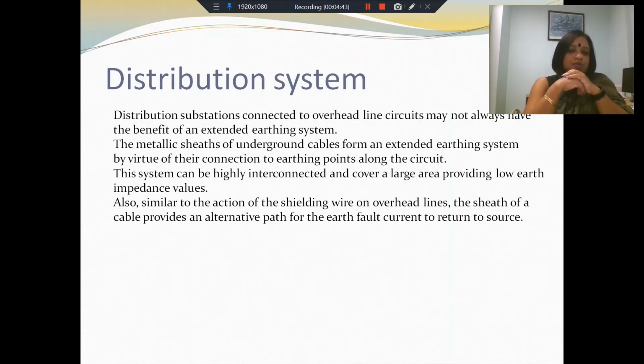But distribution systems often consist of a lot of underground cables, and the metallic sheaths of the underground cables form an extended earthing system on their own, because each of the metallic sheaths is connected to earth points along the circuit. Every few kilometers, you have an earthing point, and therefore automatically you have a distributed earth system in the cables. So the action of this is similar to the action of the shielding wires on the overhead lines. In the overhead lines, you have the shielding wire, and this shielding wire is connected to the earth at several points. Similarly, in the case of the underground cables, the sheath of the underground cable is connected to the earth at several points. So you kind of have the option of limiting the total potential rise between two points.